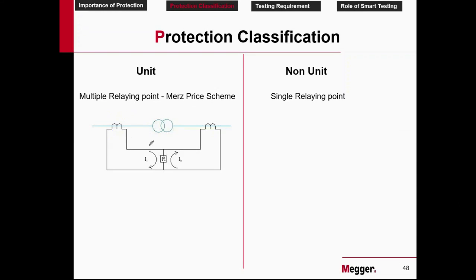Or maybe I can assume that the supply is flowing in this direction, in the primary. Normally, the CT secondary current will flow in the opposite direction. This is as per the dot convention principle. The secondary current will always flow in the opposite direction of the primary current. Or you can say that the CT secondary is earthed towards the protected equipment. So when the primary current flows from the winding to earth, the secondary current flows from earth to winding. So you can see here, this would be your earth connection, your star point CT connection.